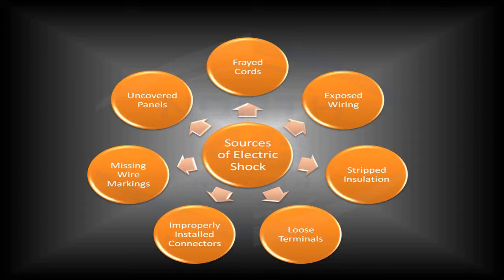Always check your terminals when you're having an issue with heat building up in a line, or potentially prematurely tripping breakers. Loose terminals are kind of a fickle subject. If you've got aluminum or copper wire going into a terminal, as soon as you apply power, there's heat inside that wire. Both metals expand and contract with varying amounts of heat. As it expands, it either crushes the wire down a little since it's already snugged up with no room for expansion, or it starts to work the lug loose on the terminal. Then once it cools down, you end up with a loose terminal.